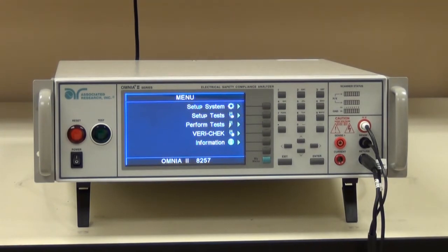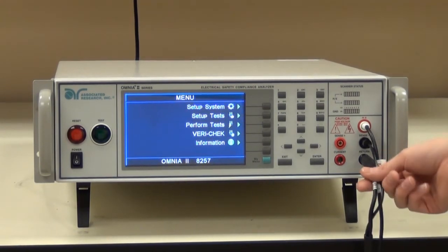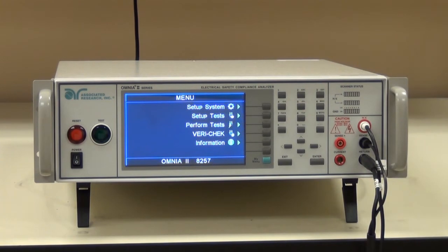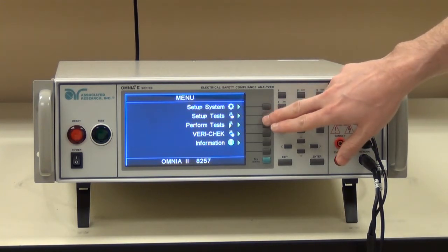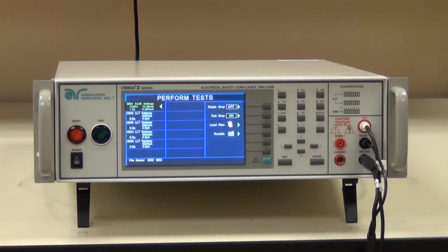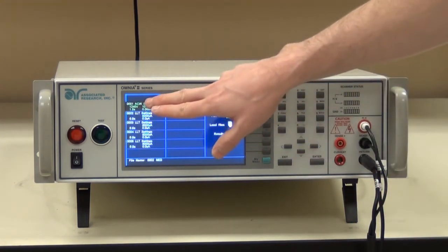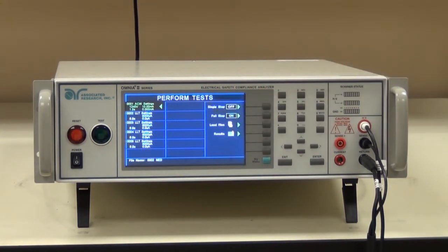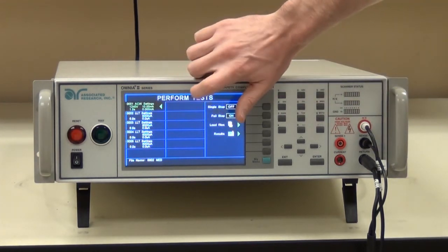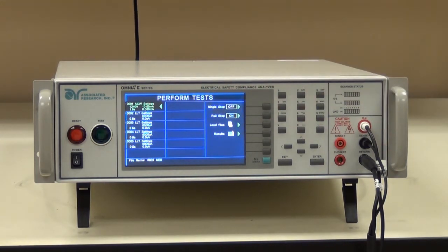The first consideration is very simple. To ensure that current isn't improperly being fed to the return, what we always recommend is that you run your hipot test prior to running your line leakage test. For example, I have a mock test set up right here, and we can see I have my hipot test first and my line leakage tests after that. This ensures that if something happens with the hipot test and the product insulation fails, you're not then going to go and run the line leakage test.